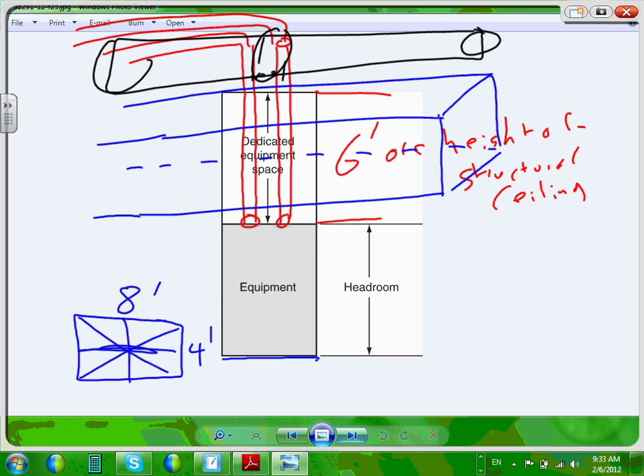So, okay, that dedicated space. The space equal to the width, above the space, shall be permitted to contain foreign systems, provided protection is installed to avoid damage to the electric equipment from condensation, leaks, or breaks in such foreign system. You have to provide some type of protection. So the rule has always been avoiding that area altogether. If you have a pipe and you need to direct your pipe, just move it away from that area altogether. And we, and our cousins, the so-called mechanical engineers, we solve this problem.